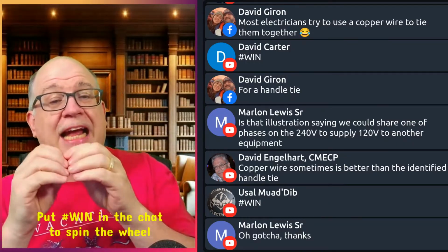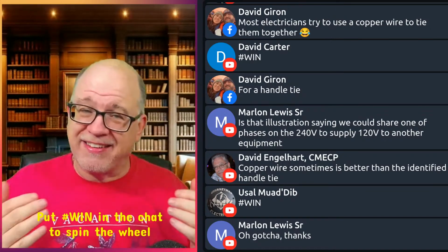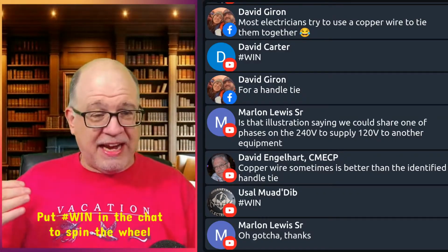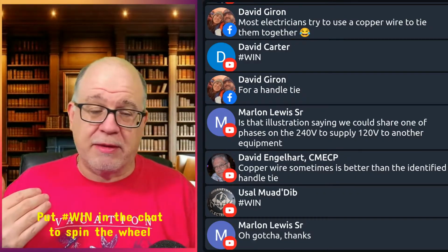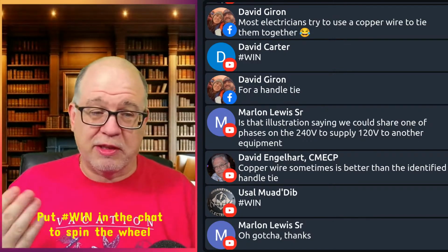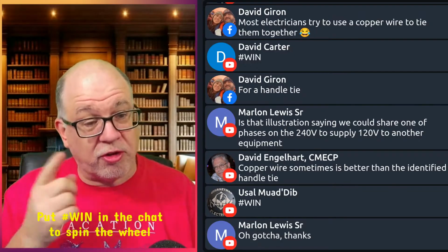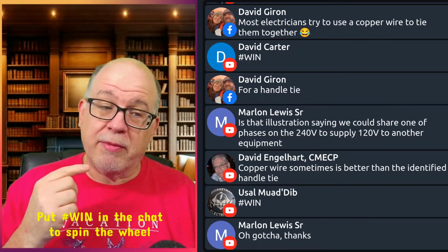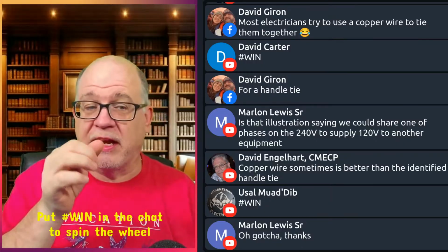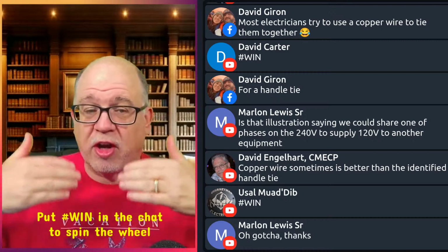The neutral has to be grouped with the actual ungrounded conductors, unless it's obvious. What does obvious mean? Well, if I have only a raceway that has a red and a black and one white, then it's obvious that that white goes with this black and that red. Okay. Now, the moment somebody may pull in additional circuits, you have to remember that when you're getting that part inspected for your work, you're going to have to now identify yours so that it's obvious with what you run, that type of thing. So this is an ongoing thing.